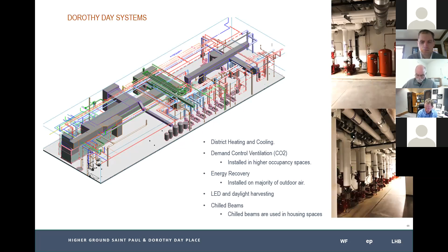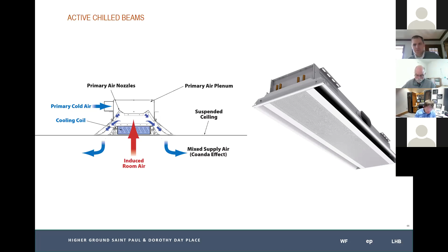But the biggest change between Higher Ground and Dorothy Day is that we determined early on we could not meet the target EUI using a fan coil system. So we switched to a chilled beam system. Here's a visual of a chilled beam. Chilled beam is just a fancy way of saying there's a coil at the ceiling level. And this is an active chilled beam where we're introducing outside air or ventilation air, and it goes through nozzles, and as it goes through nozzles, it creates a low pressure area and induces air from the room. And the big takeaway here is we don't have a fan. And that's one of the biggest savings that you get, is you don't have fan energy in every one of your units. So we went to chilled beam.